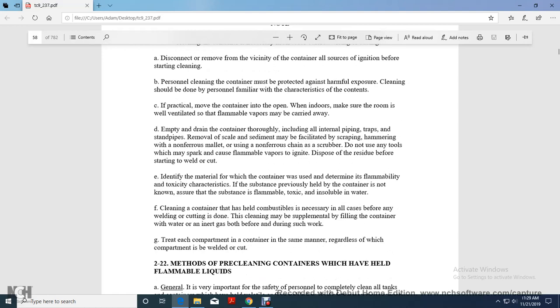Empty and drain the container through the internal piping and trap with the stand pipes. Remove the scale of the sediments. Facilitate with scraping and hammering with a non-ferrous mallet. Use a non-ferrous chain as a scrubber. Do not use any tools which may spark or cause flammable vapors to ignite. Dispose of the residue before starting the weld or cut.